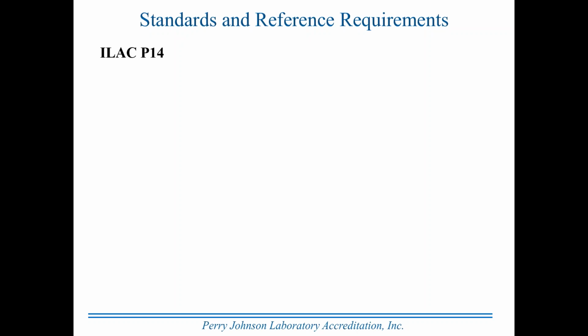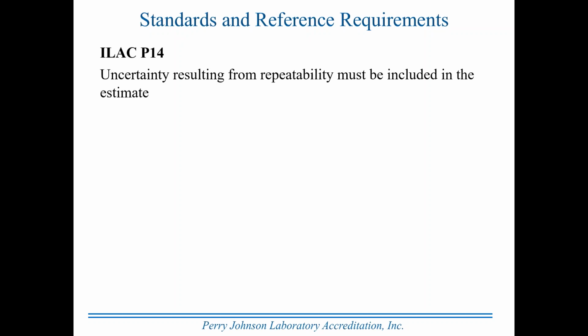All right, let's look at ILAC P14 and some of those restrictions or requirements there. Uncertainty resulting from repeatability must be included in the estimate. When we talk about repeatability, in reality, we're talking about non-repeatability. We're interested in the extent to which an instrument or a piece of equipment will not repeat a measurement. And there's uncertainty associated with that. And ILAC P14 requires that repeatability must be included in the estimate.